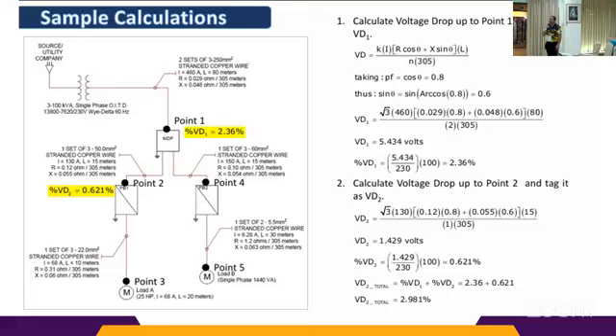From the formula, voltage drop is equal to K times I, R cosine theta plus X sine theta, times the length, divided by N, where N is the number of sets. Then divide by 305, because the resistance and reactance are given per 305 meters. That is our reference. Since the run is only 80 meters, we divide by 305 to get the exact value of the resistance and reactance. Then just substitute in the formula.